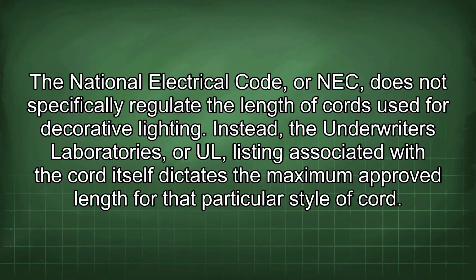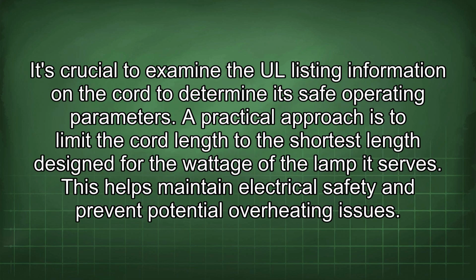The National Electrical Code, or NEC, does not specifically regulate the length of cord used for decorative lighting. Instead, the Underwriters Laboratories, or UL, listing associated with the cord itself dictates the maximum approved length for that particular style of cord. It's crucial to examine the UL listing information on the cord to determine its safe operating parameters. A practical approach is to limit the cord length to the shortest length designed for the wattage of the lamp it serves. This helps maintain electrical safety and prevent potential overheating issues.